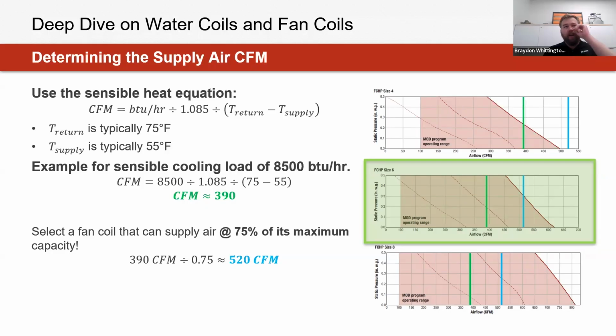So let's say 8.5 MBH here for that system. But then what we would even do when determining a certain sensible load is selecting it and making sure that it's going to have the wiggle room of being 75% of its maximum capacity. So even applying it to our required sensible load mark, just to make sure that we have that buffer range of being able to achieve what that unit's potential maximum would be there as well.